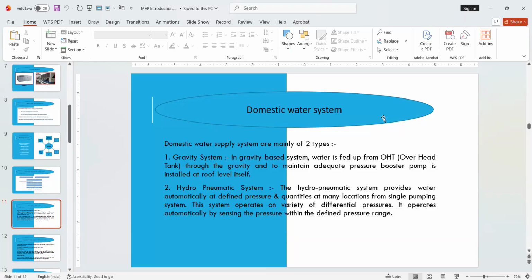This system is also in use in my home and all kinds of projects, you can see. Gravity based system. Now coming to the hydropneumatic system. A hydropneumatic system provides water automatically at defined pressure and quantities at many locations from a single pumping system. The pump is installed nearby the water tank. Outside the water tank there will be a flange, and the flange will be connected to the pump, which will be a hydropneumatic pump. And this system operates on a variety of differential pressures.